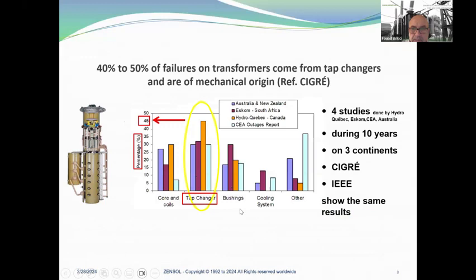40 to 50% of failures on transformers come from tap changers and are of mechanical origin. This comes from CIGRE — four studies done by Hydro-Québec, Eskom, CEA, and Australia over 10 years on three continents. CIGRE and IEEE show exactly the same results. For example, the Hydro-Québec results show 40 to 45% for tap changers.